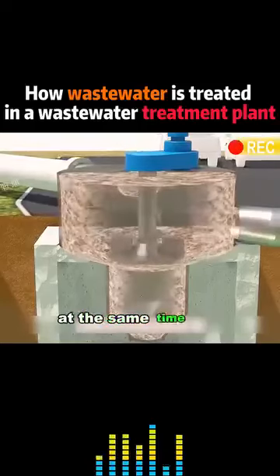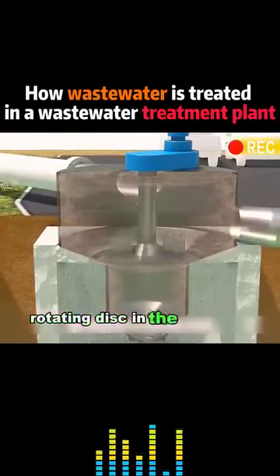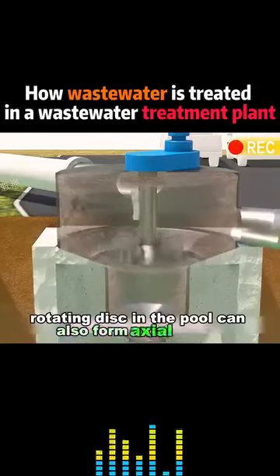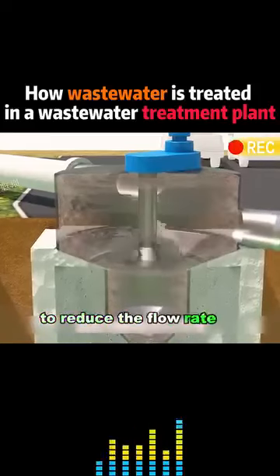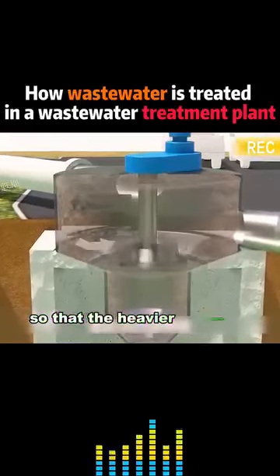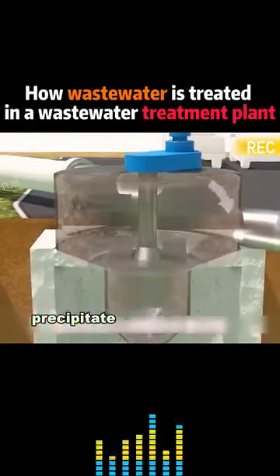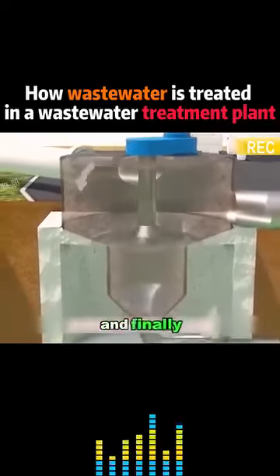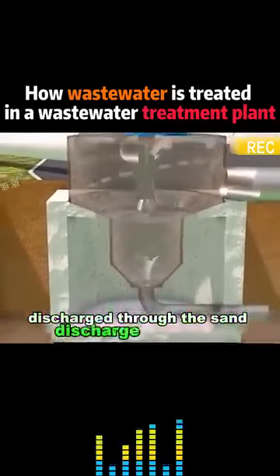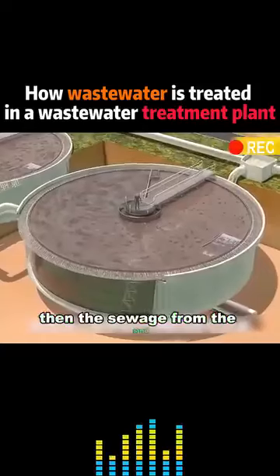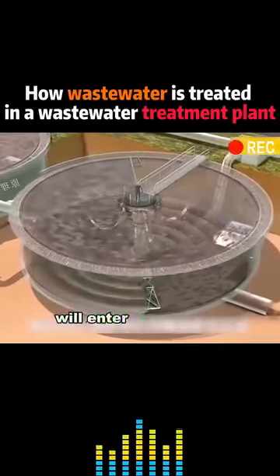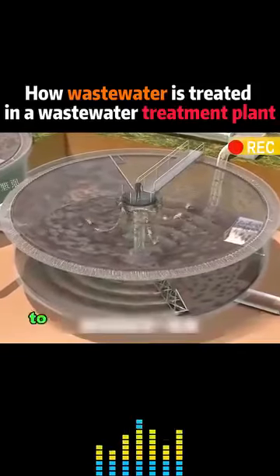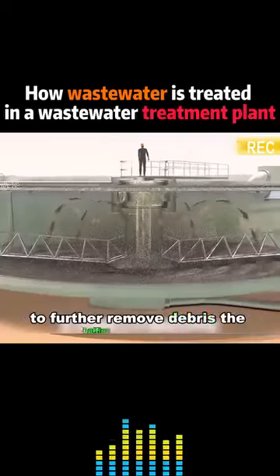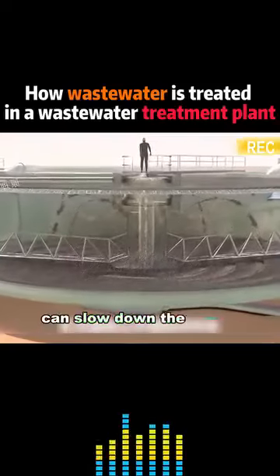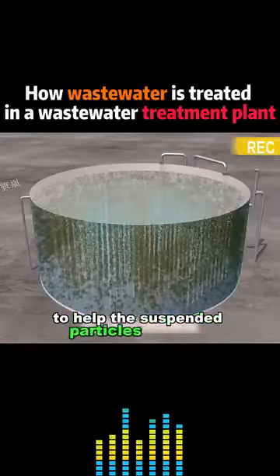At the same time, the impeller rotating disc in the pool can also form an axial vortex to reduce the flow rate of sewage, so that the heavier inorganic particles precipitate to the bottom of the pool and are finally discharged through the sand discharge equipment. Then the sewage from the sand sedimentation tank will enter the primary sedimentation tank to further remove debris. The baffles in the tank can slow down the water flow to help the suspended particles to settle.